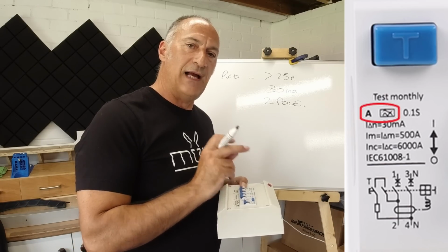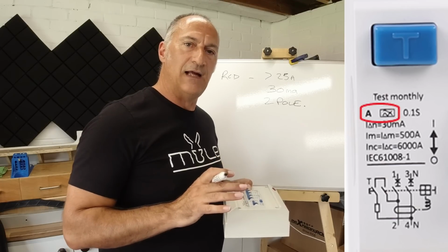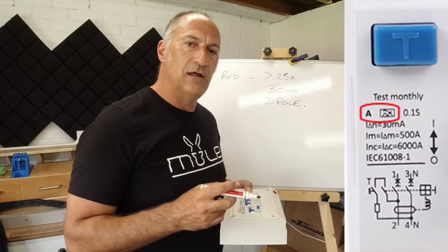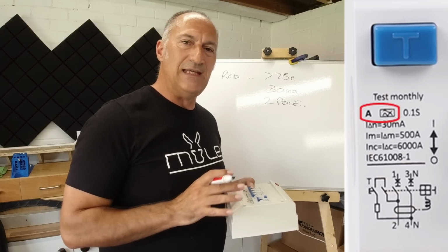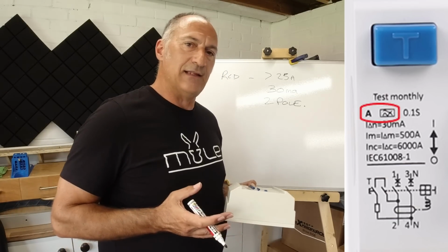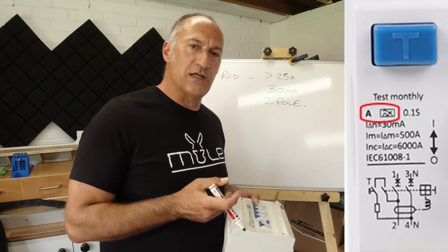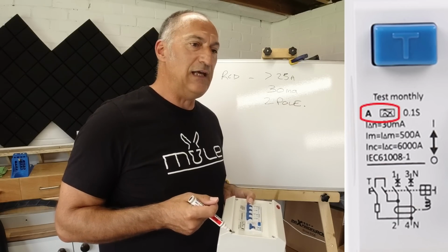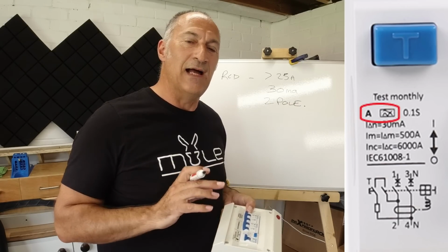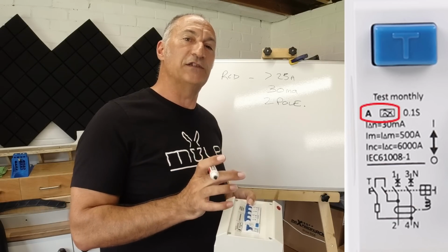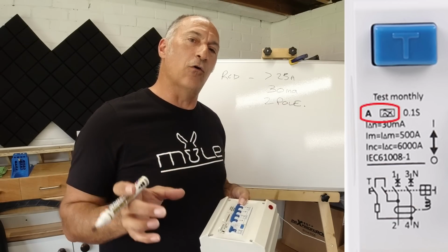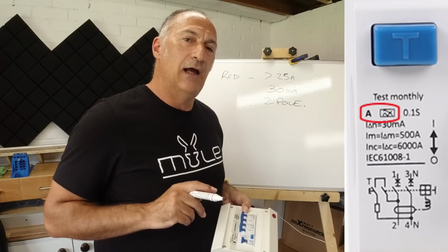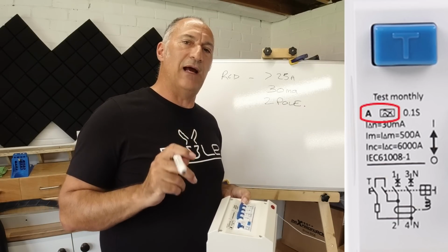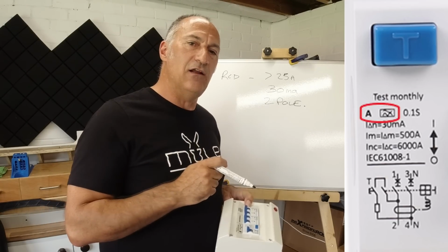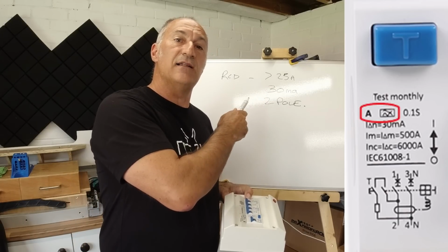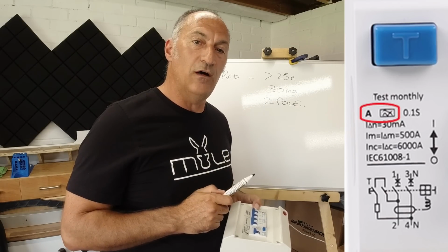Previous RCDs were type AC, so that was just for standard AC loads like heating elements, where there's no DC connected to the circuit. But nowadays we've got modern devices with microprocessor control, laptops, even simple things like washing machines. A lot of them have some level of DC control built into that AC device, and they tend to leak a small amount of DC current back down the AC line. What that does is actually stun our RCD, preventing it from working.